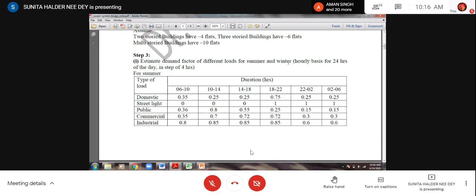So that's why winter data is also required. Otherwise, if we only want to design the distribution system, then summer data is sufficient, because in our summer-driven country, the demand factor during summer will always be more than winter. Okay, and we have to decide the size of the transformer from the maximum demand. Understood my point?